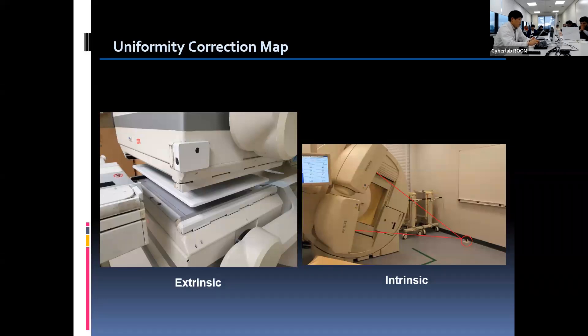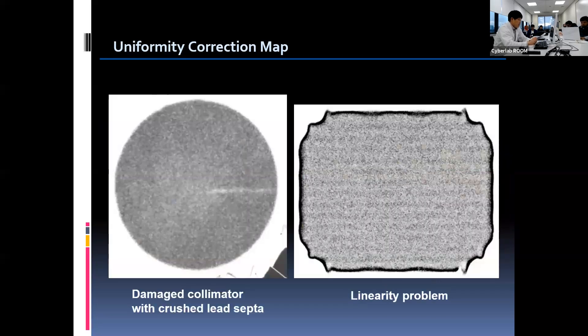However, technetium is more ideal for uniformity calibration due to the fact that technetium is the actual radioisotope we are using for clinical imaging. The frequency of testing depends on manufacturer's recommendation and camera condition. We usually acquire the correction map monthly, as long as the condition of the camera is not poor. Extrinsic uniformity correction may solve the problem posed by a defective collimator, as shown in the left image. Intrinsic correction can take care of a linearity problem, as described in the image on the right.